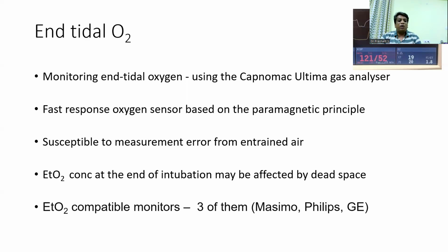But there are some monitors which are compatible with end tidal oxygen monitoring, like Masimo, Philips, and GE monitors. Basically, they use the Capnomac Ultima gas analyzer with a fast response oxygen sensor, which is based on the paramagnetic principle. Again, these are susceptible to measurement error from entrained air.